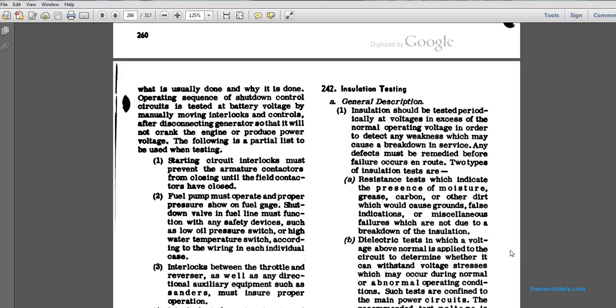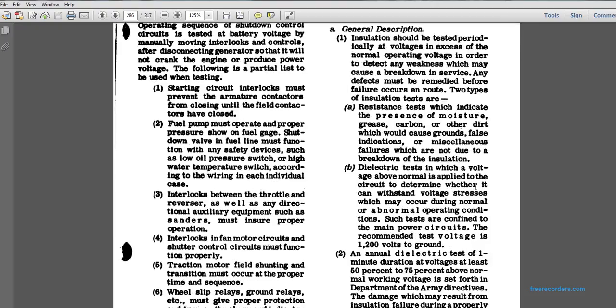Insulation should be tested periodically at a voltage in excess of normal operating voltage in order to detect any weaknesses which may cause a breakdown in service. Any defects must be remedied before failure occurs. The two types of insulation testing are resistance tests, which indicate the presence of moisture, grease, carbon, and other dirt which cause false grounds, false indications, or miscellaneous failures which are not due to the breakdown of the insulation.